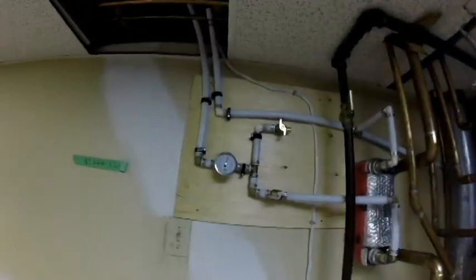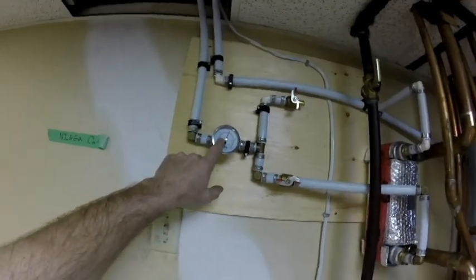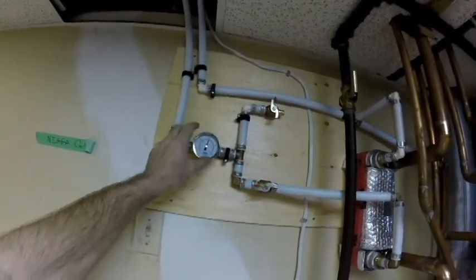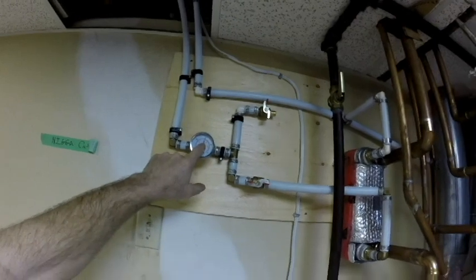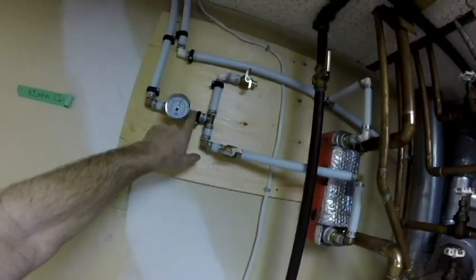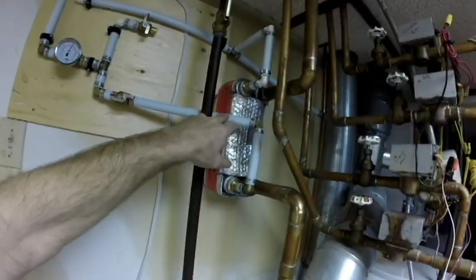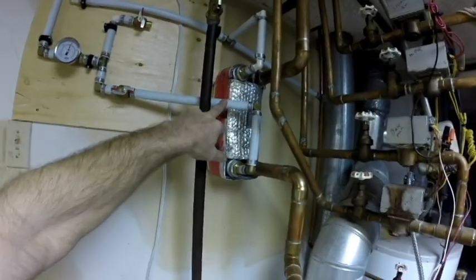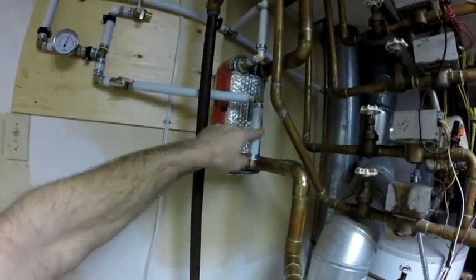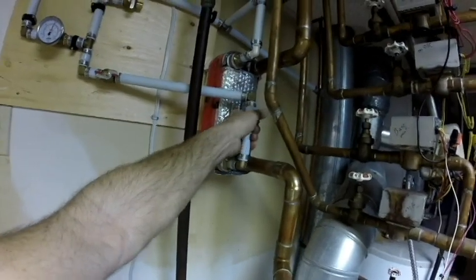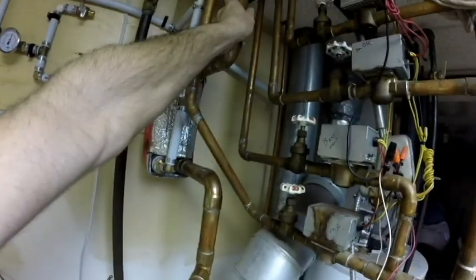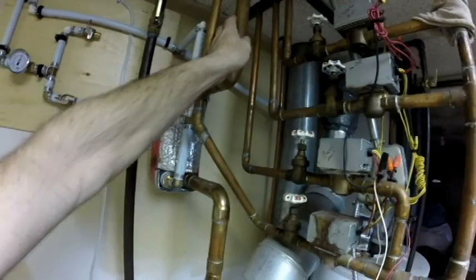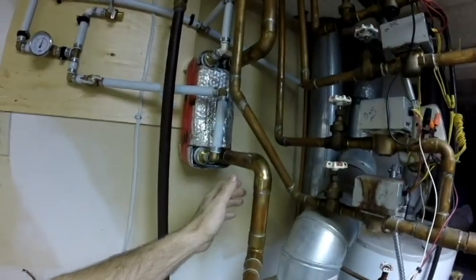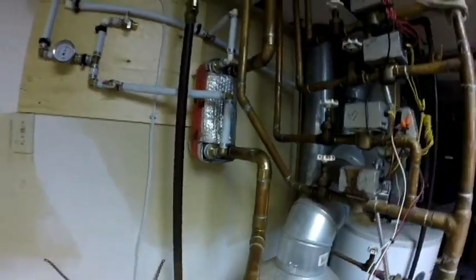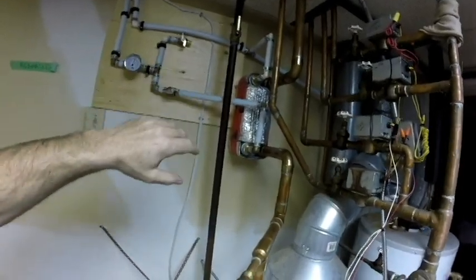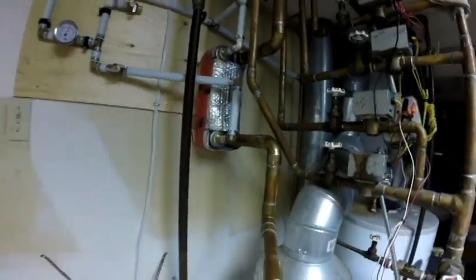So anyways, this is the temperature of the water now coming in from the storage tank outside, and you can see here it's at 150 degrees Fahrenheit. Then it passes through here, which goes through a 20 plate heat exchanger, which is capable of transferring 330,000 BTUs per hour. Basically, the water on this line will be cold, and this line will be so hot in one pass that you can barely touch it. That's how much the water can heat this system through this plate exchanger.